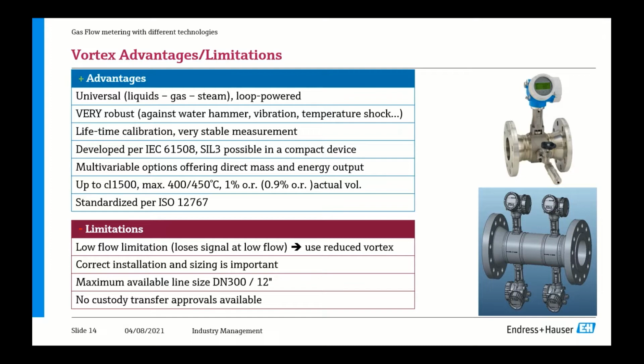The most important limitation of this technology, however, is the low flow limitation. You lose the signal at low flows. That's why you should, in those cases, use a reduced bore vortex meter and or do a good sizing. The maximum line size is DN 12-inch, and we don't have custody transfer. So thanks a lot. That was it from the basics and vortex side.